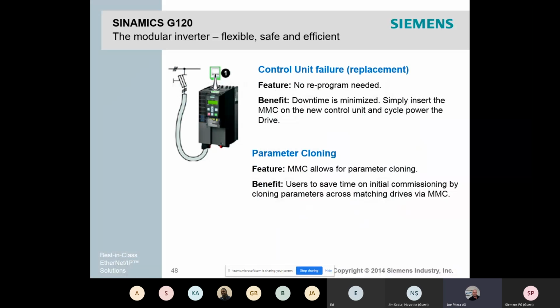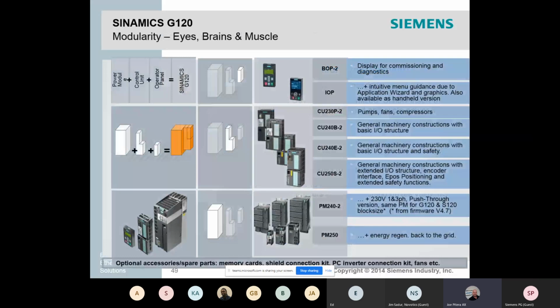When a user inserts the memory card to copy the parameters, everything is copied except the communication parameters. So if you have multiple drives in a lineup for, say, a conveyor belt, you could just commission one drive, copy the parameters to a memory card, and then put the memory card in a second drive, let it boot up, and it will automatically read all the parameters and commission the drive without even connecting to it.